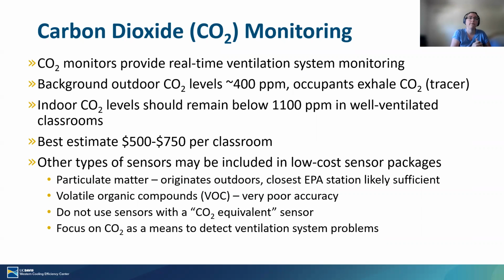And what I really advocate for is that the carbon dioxide reading should be displayed to the teacher and the occupants of the classroom, such that people can have a visual check that the ventilation system is working. Best estimate on cost is somewhere between $500 and $750 a classroom to have a system installed, and that generally has some connection to facilities, because facility managers are going to want that CO2 data going back to their building automation system or some central dashboard, such that they can flag issues perhaps even before they get a teacher complaint.